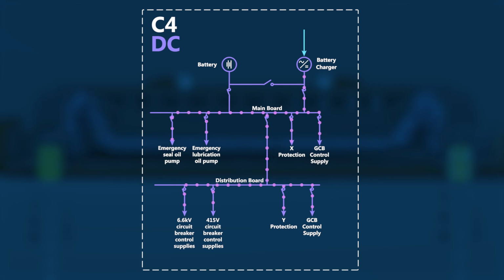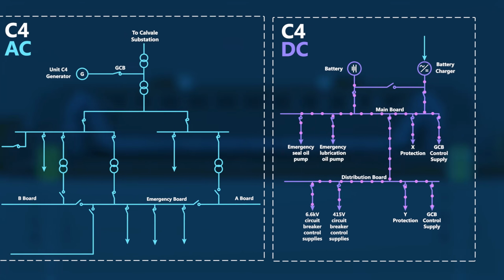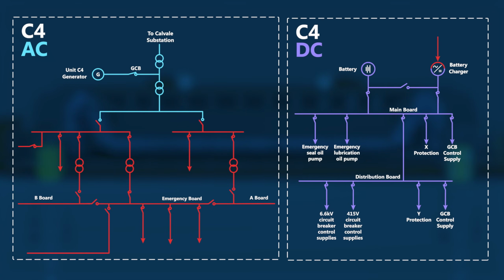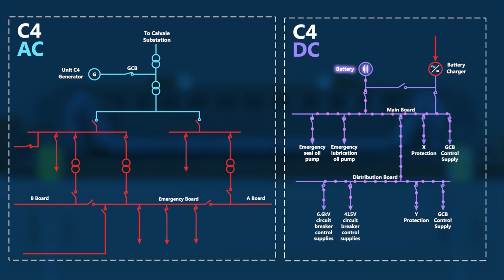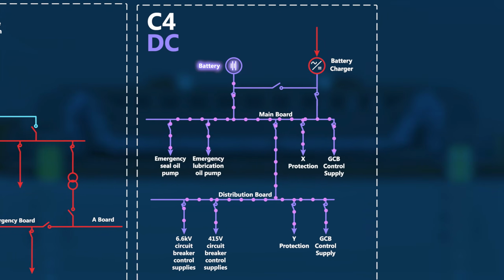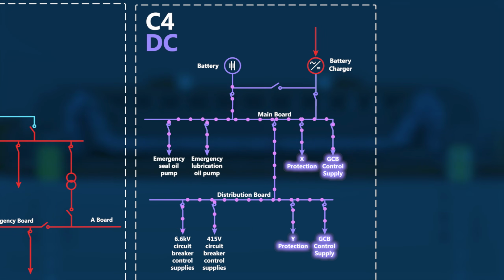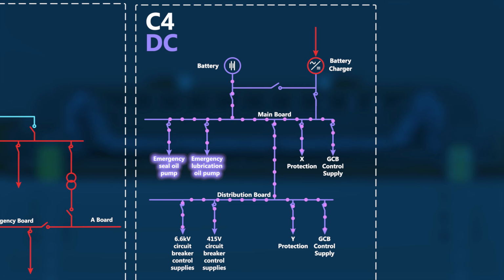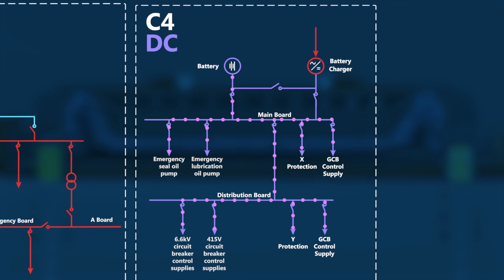This system is primarily powered by a battery charger, which also keeps a battery fully charged. This battery provides important redundancy. If ever there was a loss of AC power, which would result in the charger ceasing to operate, the battery could continue to power the DC system. The DC therefore would still monitor, control and protect the unit, and its backup pumps would continue to supply lubrication oil and seal oil to the turbine generator.